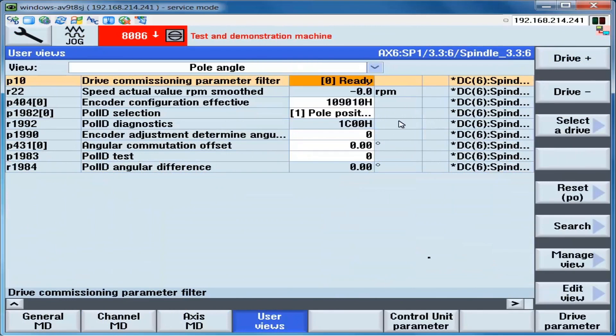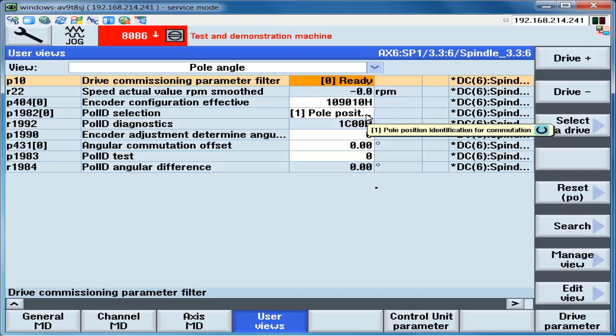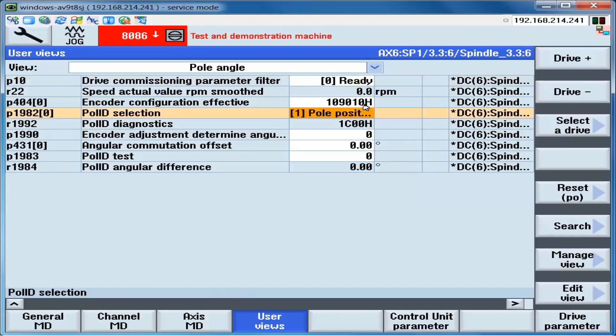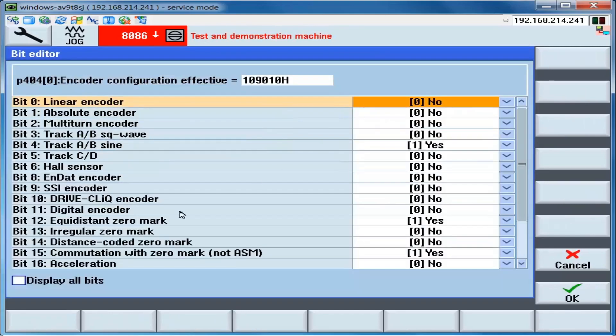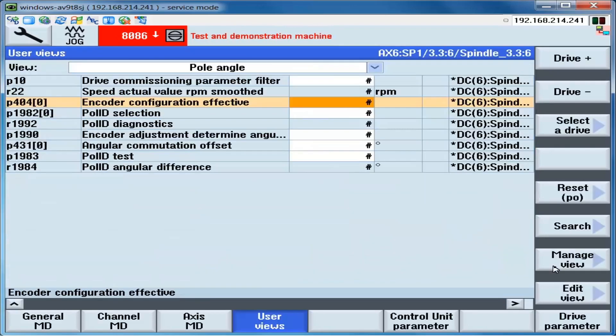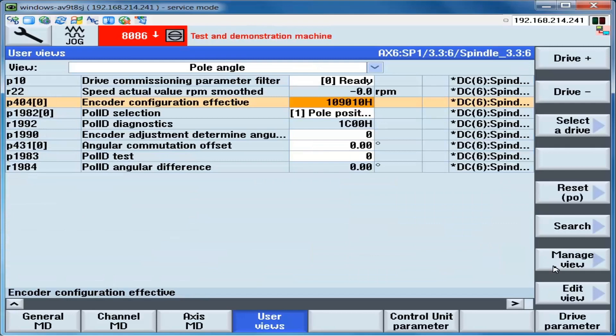Before beginning, we make sure we have selected the correct axis. In this case, our spindle. We will check to see that the settings make sense. Normally, P1982 is set to a 1. And P404 bit 15 is set to a 1. These two settings require that the Pole Angle be set via P1990.